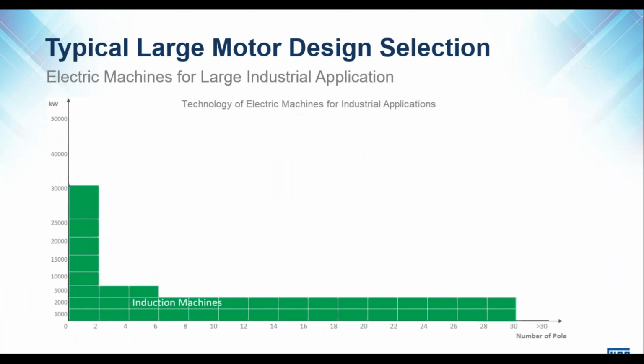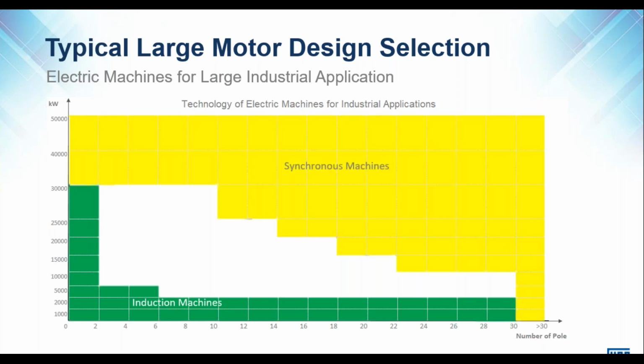So to set the tone, we talk about induction motors. We've drawn a scale here of megawatt versus speed. In general, induction machines would be useful in applications of low to medium power in high speed, that is low number of poles, and right up to medium power in low number of poles. On the other side of the spectrum, synchronous machines find their applications generally in very high megawatt ranges, and they are particularly useful in high megawatt low speed applications. That's very high number of poles, anything 20 poles and above.